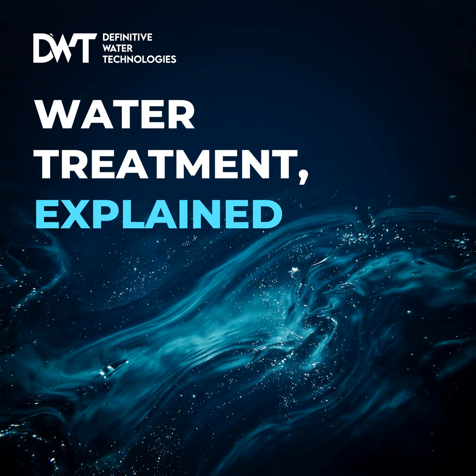Right. Liquid, gas bubbles, whatever. It just pushes the gas bubble straight through into the process. It self-primes incredibly reliably. So if the complaint is the pump loses prime every afternoon, the fix is a peristaltic pump. Or a highly specialized degassing head. Yeah. But the fix is never buying a bigger standard diaphragm pump. Okay, distilling this for our South African technician. Solenoids for standard small stuff, motor-driven for big continuous duties, and peristaltic for gassing chemicals like hypochlorite.